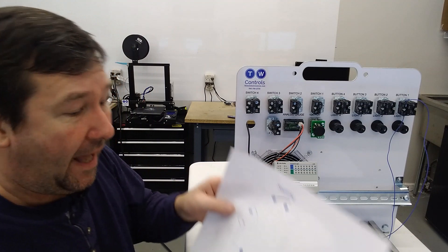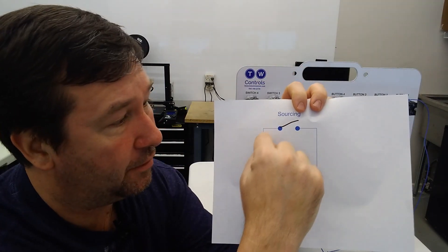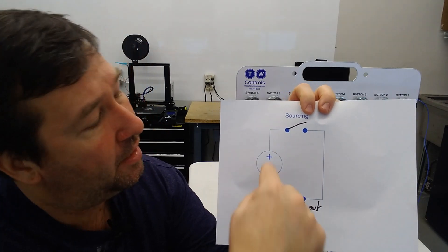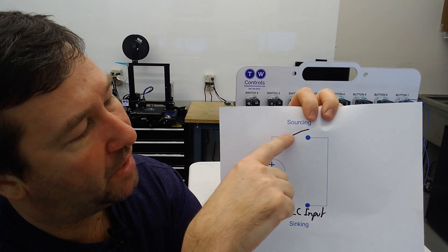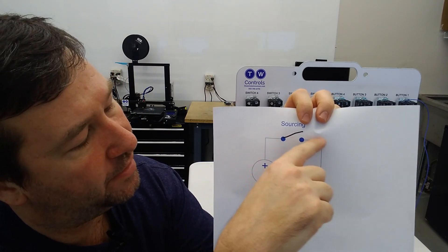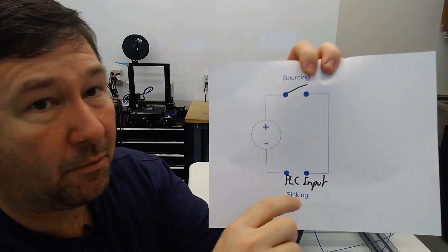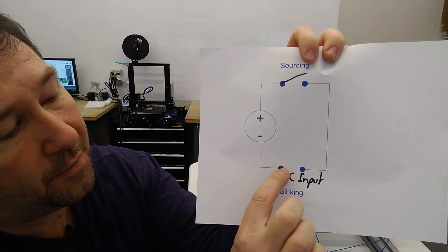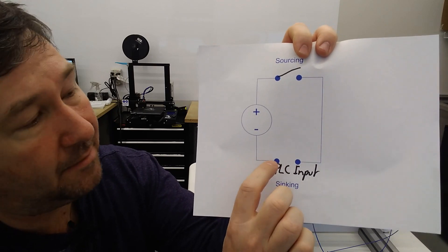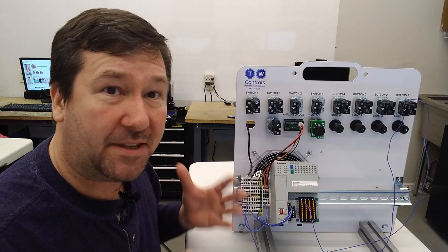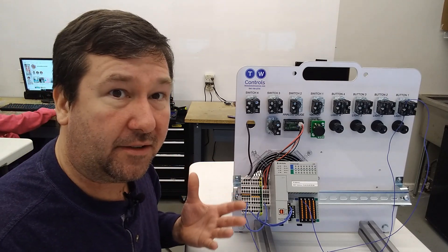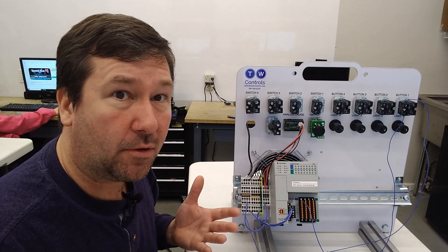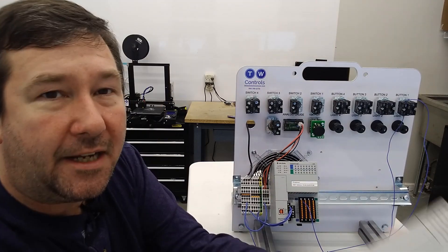A lot of people say, okay, we're done. We're not. Because going back to that sinking and sourcing video, remember, we have to have current flow through our PLC input for it to work. So right now, we've got a wire from the plus of our power supply up to our switch. Then we go from the other side of our switch to our PLC input. But what we've left out is this little bit of wire here from the other side of the PLC input back to the minus of our power supply.